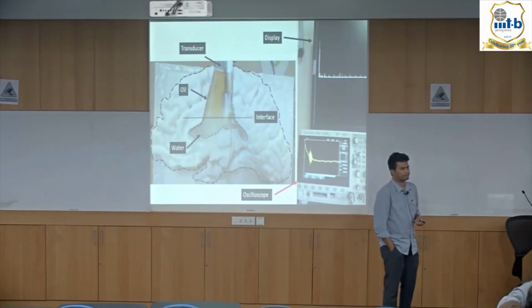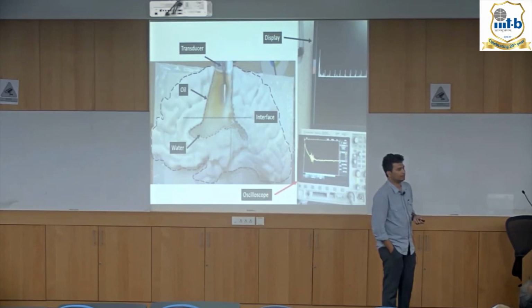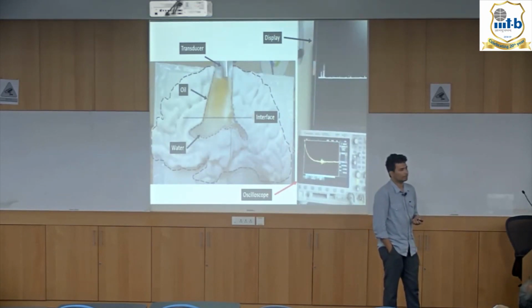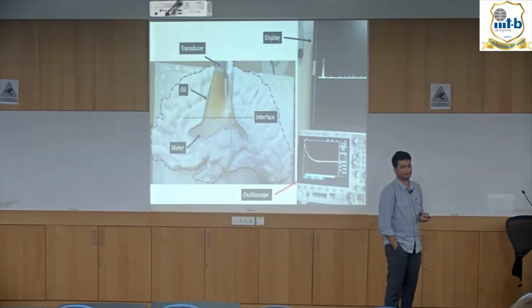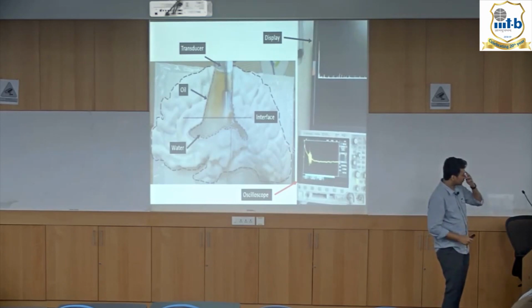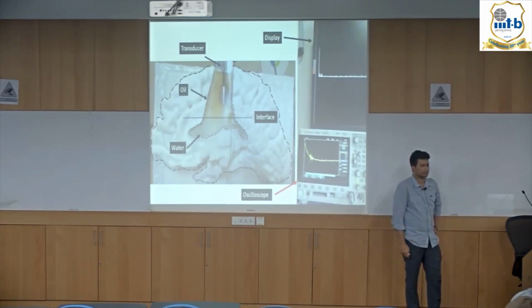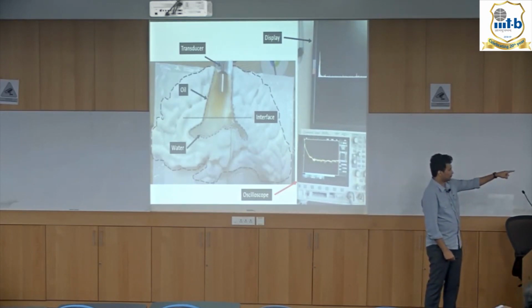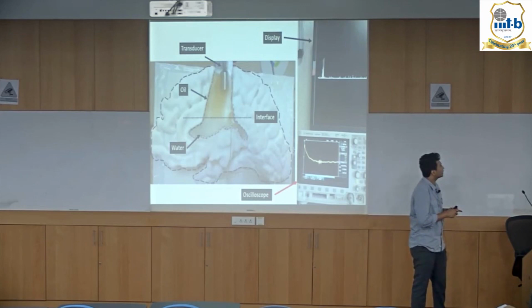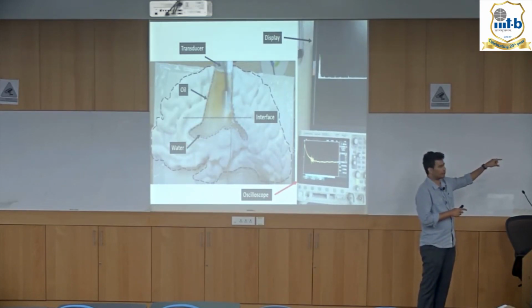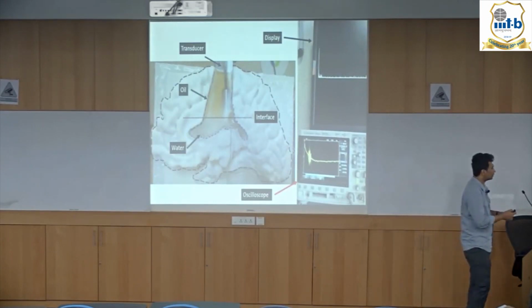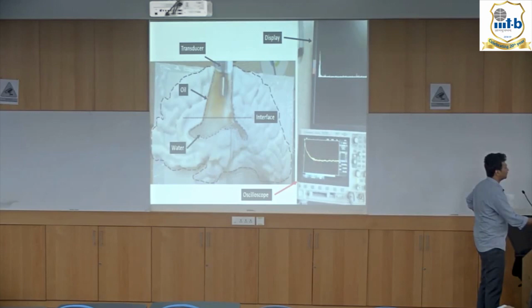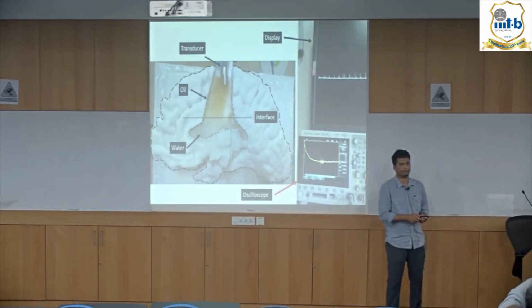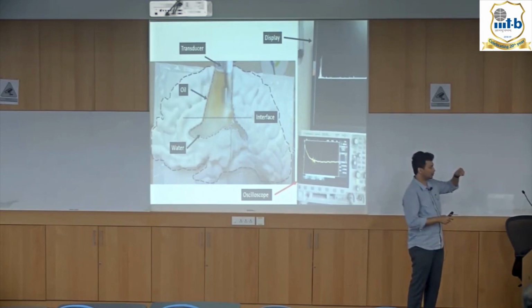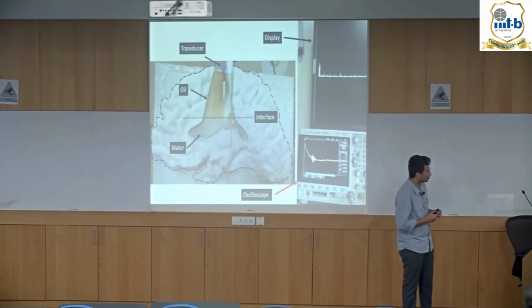You can also know whether you're moving closer to the ventricles or away from the ventricles. And you also get multiple echoes, which tells you the depth. In the oscilloscope, top wall and bottom wall both, you can see two peaks, where one peak corresponds to the interface between oil and water, and another peak corresponds to this part. That is an indication that there is another bottom wall. Since we were holding the transducer manually, there is a lot of shaking in the hand. That's why there's wobbling of the echo.